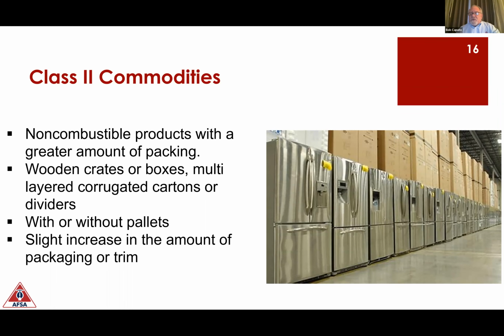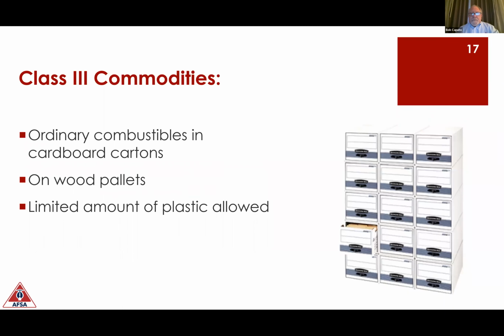Now you might ask yourself, why in the world is Bob telling me this level of detail? The answer is, I want you to see that these subtle differences in the carton or the container are going to drive a different requirement for the fire sprinkler system. So if you're moving a tenant into a building, we need to know a lot of specific stuff so that we can understand what the fire sprinkler system needs to be. Is the existing system adequate, or will upgrades be needed, and how will those upgrades be handled before your tenant can move into the building?